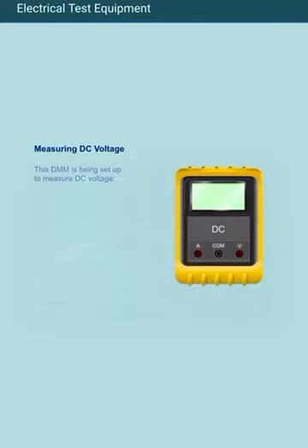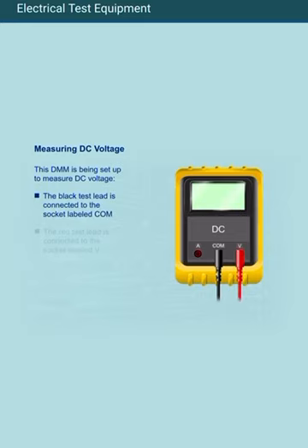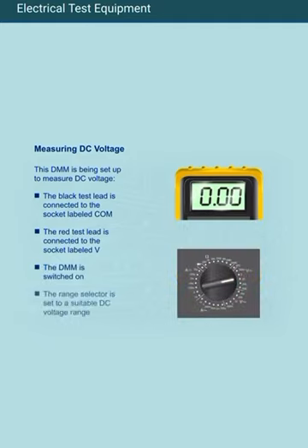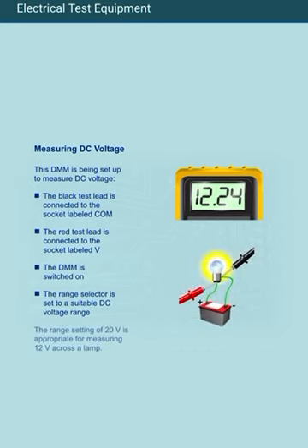Measuring DC voltage. This DMM is being set up to measure DC voltage. The black test lead is connected to the socket labeled COM. The red test lead is connected to the socket labeled V. The DMM is switched on. The range selector is set to a suitable DC voltage range. The range setting of 20 volts is appropriate for measuring 12 volts across a lamp.